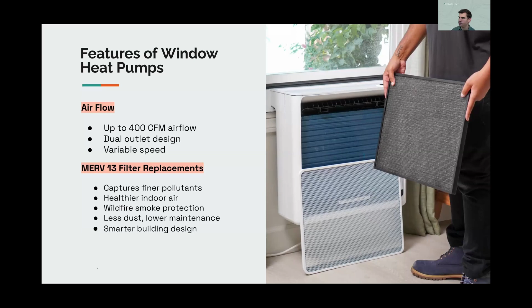That large cross-section for airflow means quieter indoor fan, and it also means you can add air filtration. So you can drop in a MERV 13 filter and start to do air quality control as well. And so airflow is really much improved in these systems. It leads to more quiet systems. It leads to better room mixing and better distribution of temperature and therefore comfort, and leads to better air quality.